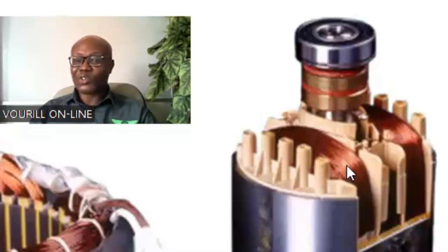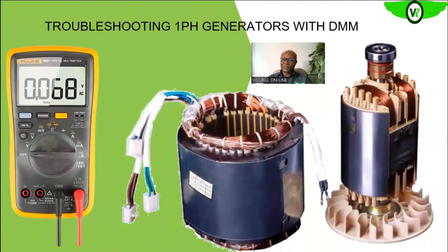And you also test the resistances of this winding. If it is something that you have been doing before, you know their resistances, so you compare it with what you know to ascertain that it has not shorted. Because if it is shorted, the resistance is less than what you used to have or what is supposed to be there normally. It means that there's a short within those windings. It is the same with the exciter, with the main armature and the exciter armature. You test for the resistance. You see they are insulated from the yoke. You test for short to ground, and then you test for continuity. So that is the test that you carry out on the single phase generator with your digital multimeter.